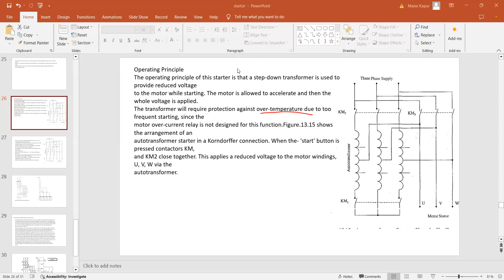Auto transformer starter is in a closed transition connection. When the start button is pressed, contactor KM1, this is KM1, okay, and KM2 close together. So KM1 and KM2 will close together, and this will apply reduced voltage to the motor by the auto transformer. This much is clear?